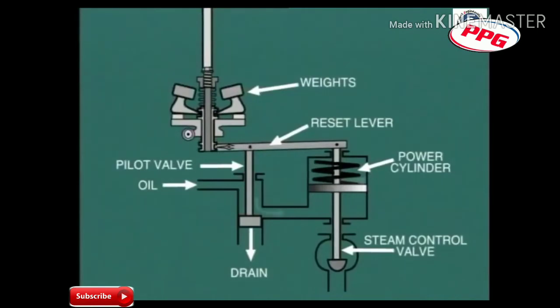This in turn allows more high-pressure oil to enter the power cylinder and raise the piston against the compression spring. This movement of the power piston opens the steam control valve and allows more steam to enter the turbine, which causes its speed to increase.